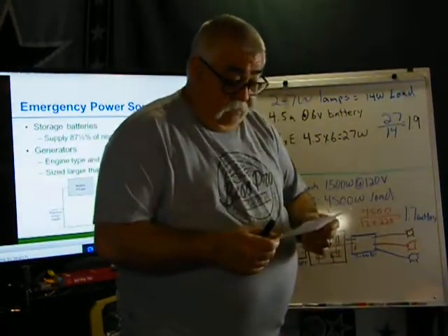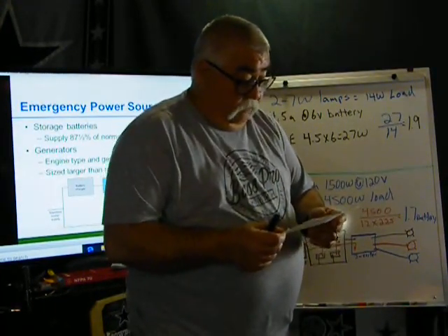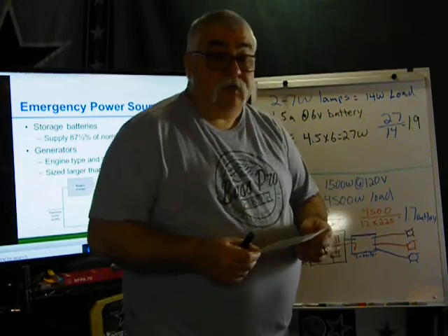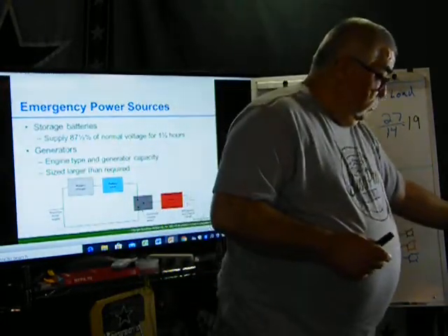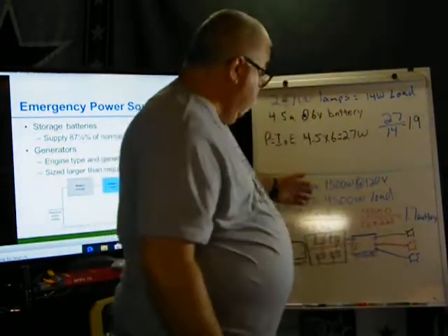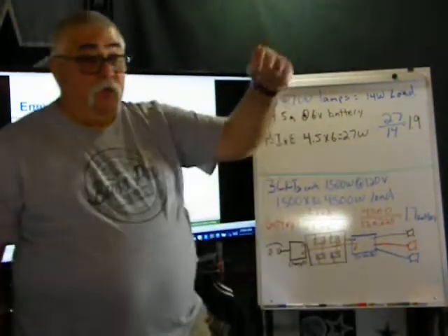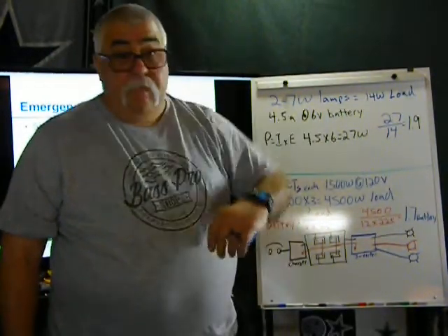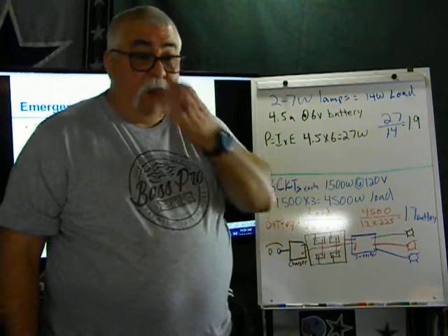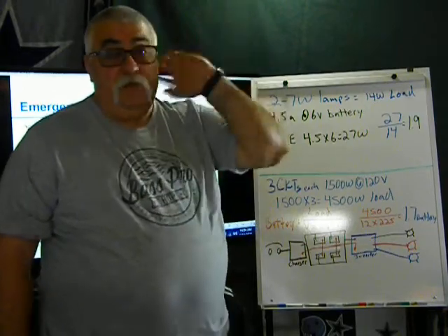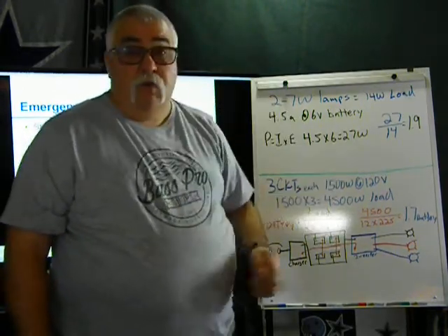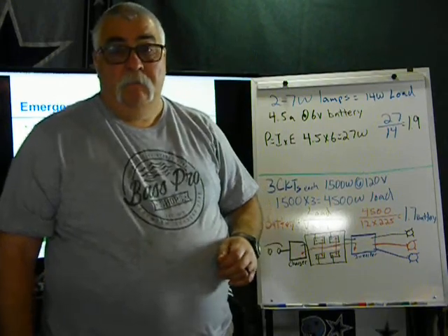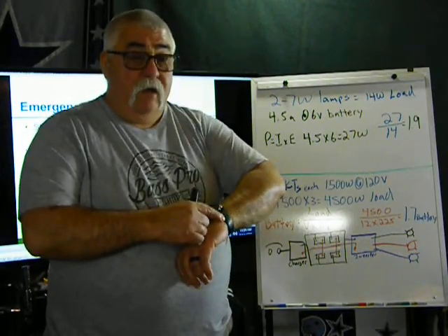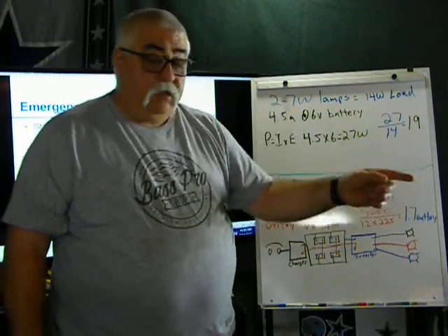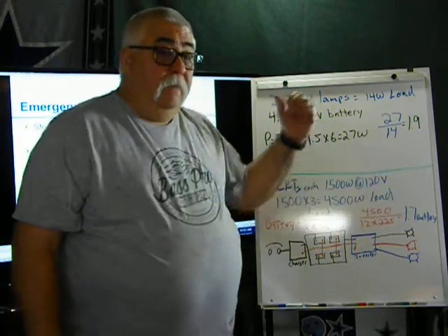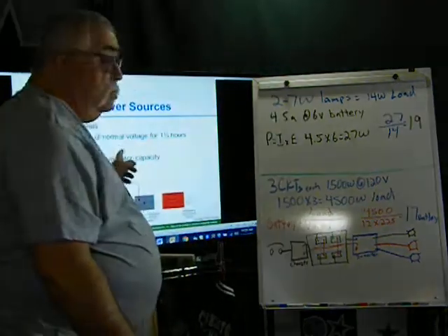It says once a year, each unit should be tested for the full duration of 90 minutes. So that means if these are on a separate breaker, just like I have them here, guess what? You go turn those breakers off. Come back in about an hour and a half, or an hour and 15 minutes. Now you start walking the floors to see which ones are on and which are not. Why? Because if at an hour the lights are already going out, that means the battery is not holding its charge and you're not maintaining the hour and a half.